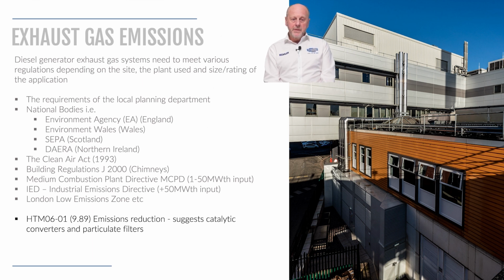Elements of emissions reduction requirements in HTM06 in section 9.89 has been misleading consultants for a long time, as it prescribes the use of catalytic converters and particulate filters, the use of which depends on the engine, the age of the engine, the application, and what else is on site. So the guidance is very, very minimal here. The only potential requirements are to comply with the Medium Combustion Plant Directive and the Clean Air Act and building regulations. So let's look at the issue of emissions.